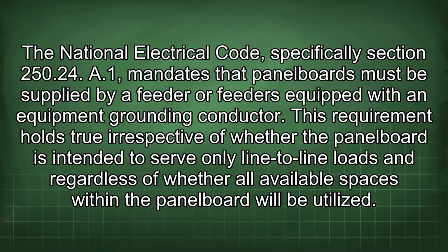The National Electrical Code, specifically Section 250.24(A)(1), mandates that panel boards must be supplied by a feeder or feeders equipped with an equipment grounding conductor. This requirement holds true irrespective of whether the panel board is intended to serve only line-to-line loads and regardless of whether all available spaces within the panel board will be utilized.